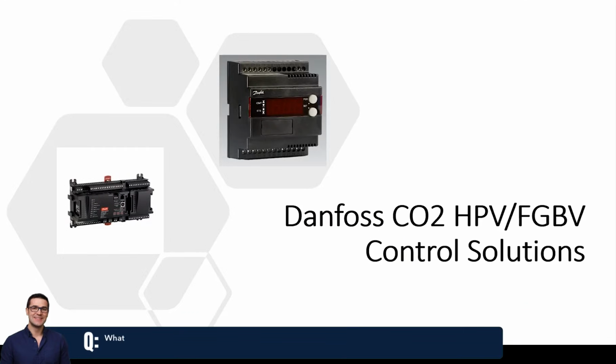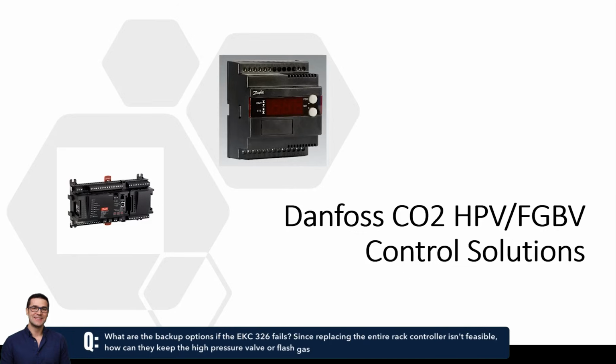So what are the options right now? If an EKC 326 fails, what are the options? Because I know you guys have multiple options for these pack controllers. Say they have all the setup and this controller fails, what would be the best option? Because you're not going to change the whole rack controller at that point. How can they get those two valves up and running, the high pressure valve and the flash gas bypass valve?